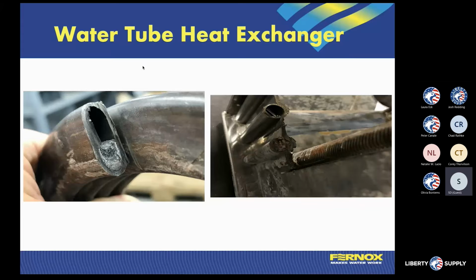And then we have obviously lower flow. So that means the water is sitting in that heat exchanger for a longer duration, creating an overheated component, which is going to put additional stress on that metal. So it doesn't matter if it's a water tube that's a flattened tube or a circular tube, you're going to have issues with any type of heat exchanger that has water quality that is not proper for that particular system.